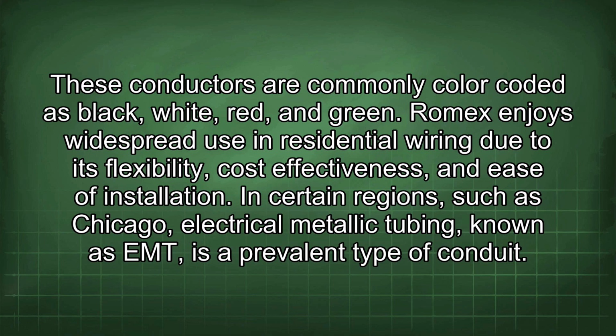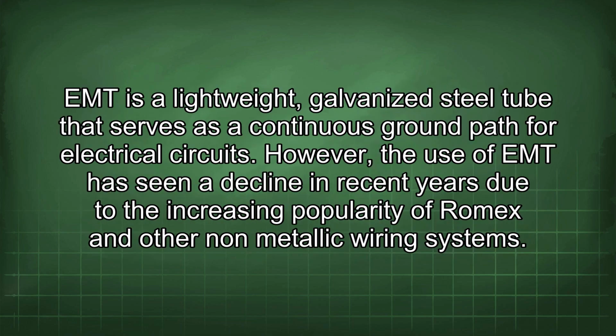In certain regions, such as Chicago, electrical metallic tubing known as EMT is a prevalent type of conduit. EMT is a lightweight, galvanized steel tube that serves as a continuous ground path for electrical circuits. However, the use of EMT has seen a decline in recent years due to the increasing popularity of Romex and other non-metallic wiring systems.